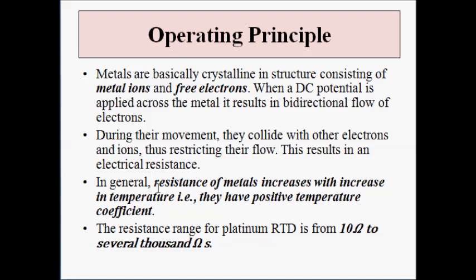The resistance of the metal increases with an increase in surrounding temperature. The movement of electrons and their collision with other metal ions and free electrons causes electrical resistance, which is directly related to the surrounding temperature. When the surrounding temperature increases, the electrical resistance of metals increases, and when the surrounding temperature decreases, the electrical resistance also decreases. This is called the positive temperature coefficient of metals used for fabrication of RTD.